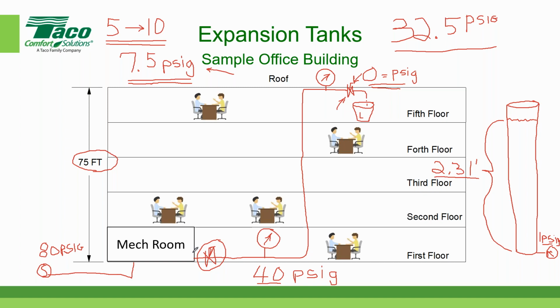Now I haven't set the pressure regulating valve yet. I just wanted to fill the system until I got to 40 PSIG. And then I went back and I set the discharge pressure of my pressure regulating valve so it would always give me 40 PSIG as a minimum pressure in the system. So does that help clarify that, Brett? Yep.